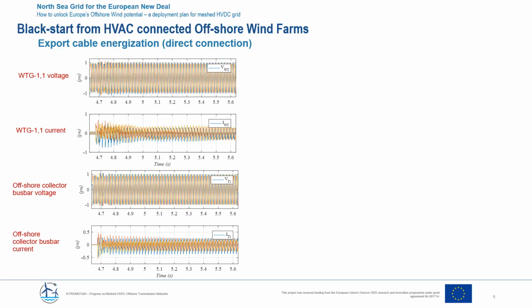Here you can see some results. On the left, you have the export cable energization. This is directly connected. You see the voltage seen by the wind turbine, the current seen by the wind turbines, and the offshore collector busbar voltage and currents. And you see that the direct connection is causing quite a lot of harmonics and resonance between the transformer and the cable.